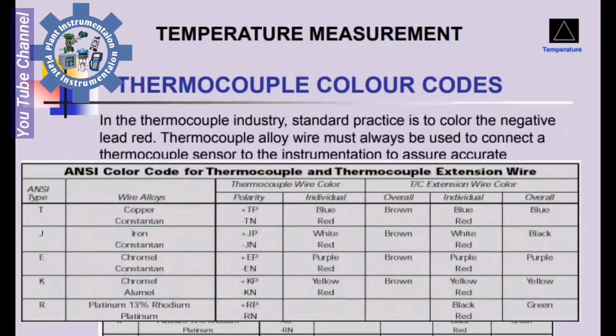ANSI type T wire alloys: copper-Constantan. Thermocouple wire color: TP positive, TN negative. Individual: blue, red. Overall: brown. Thermocouple extension wire color: blue, red. Overall: blue.